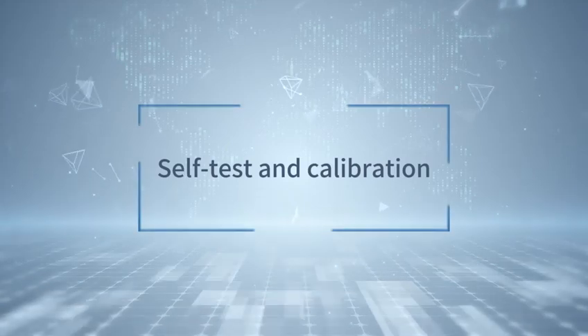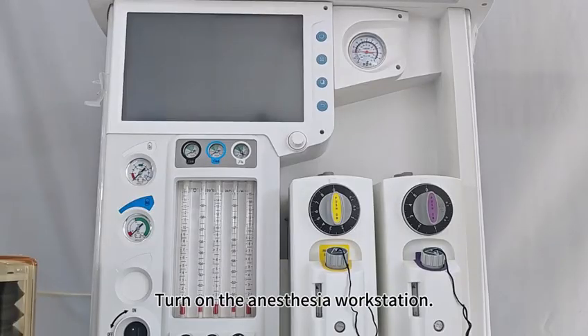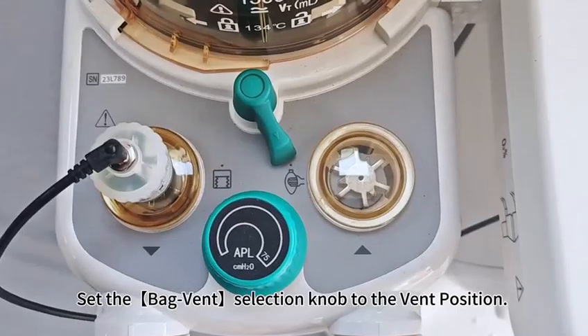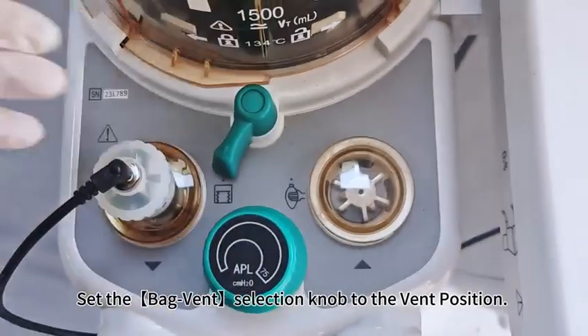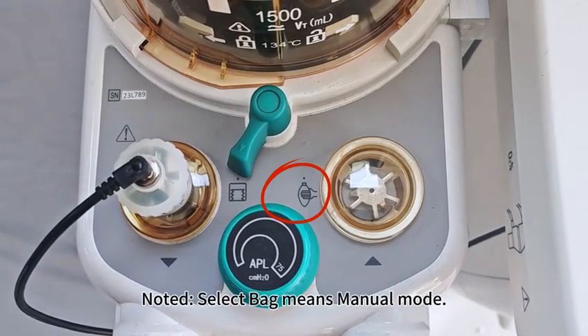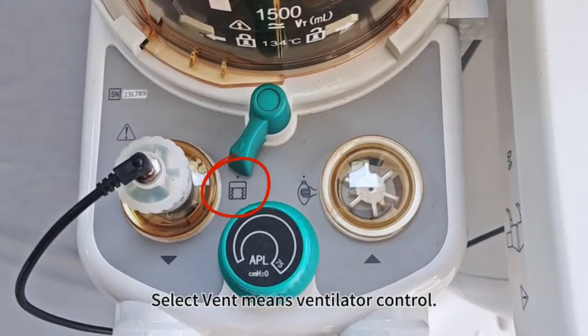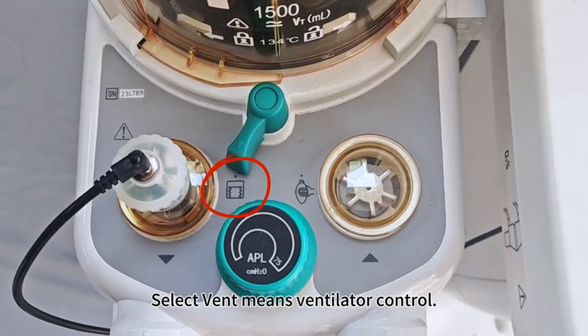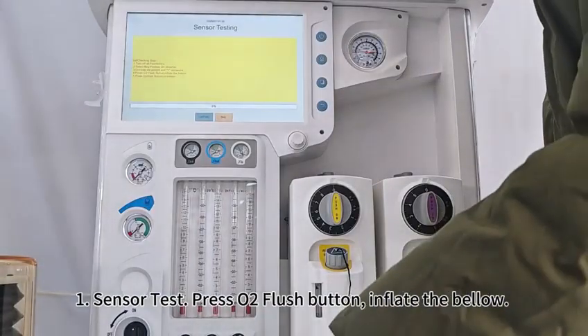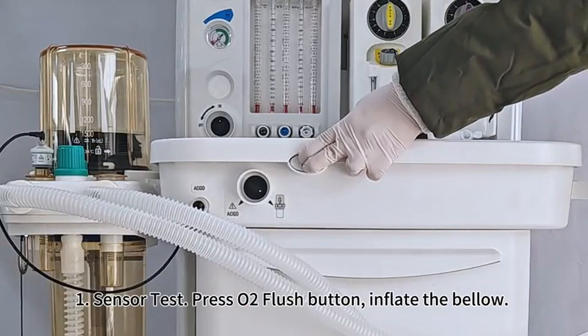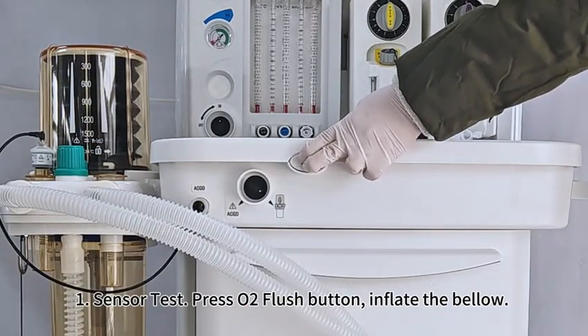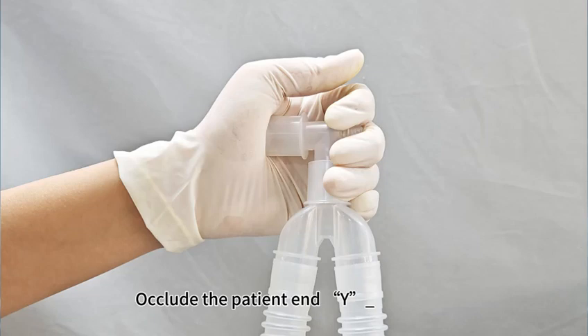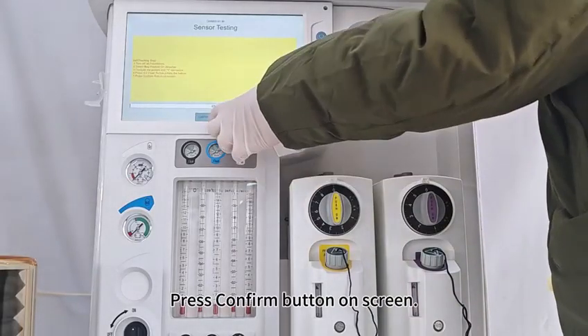Self-test and calibration. Turn on the anesthesia workstation. Set the bag vent selection knob to the vent position. Noted, select bag means manual mode. Select vent means ventilator control. First, sensor test. Press oxygen flush button, inflate the bellow. Occlude the patient end Y-piece connector. Press confirm button on screen.